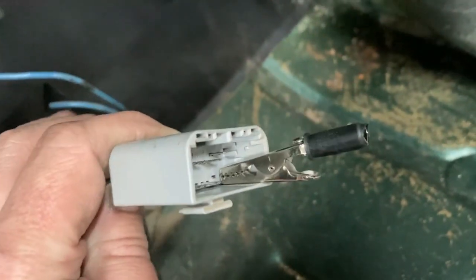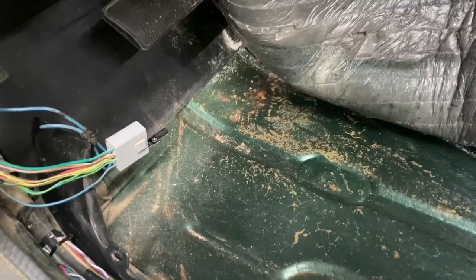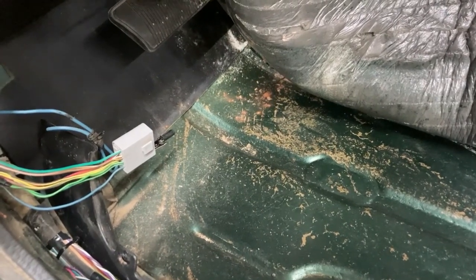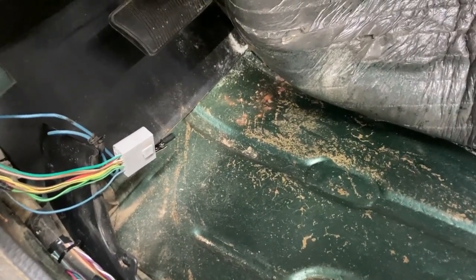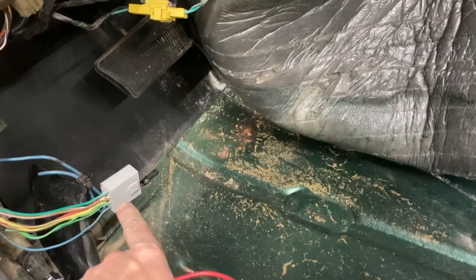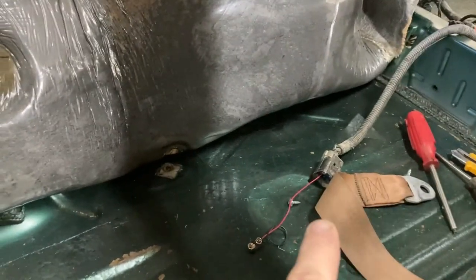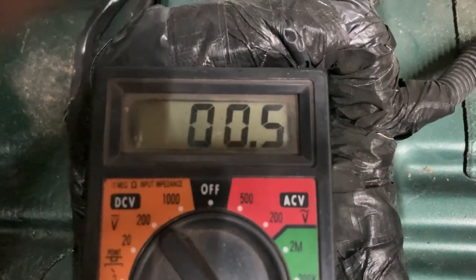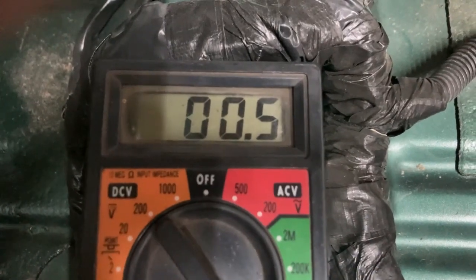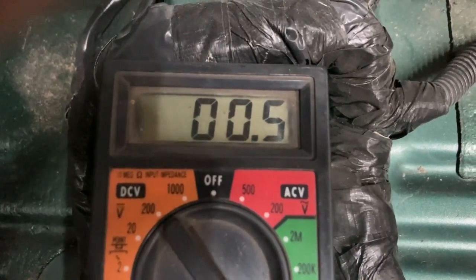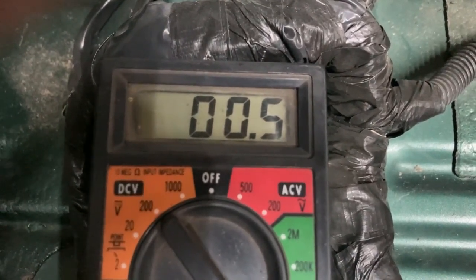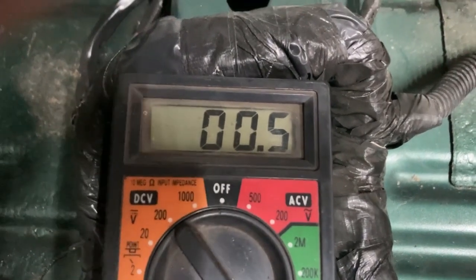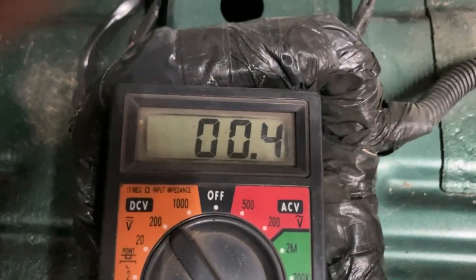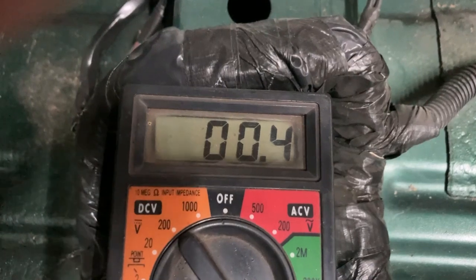I just got that alligator clip on the pin there, and I'm checking for continuity or resistance to make sure we have power from this end to that end. It looks like we're at around 0.5, which is good. The lowest reading I've received so far is about 0.3 - usually 0.3, 0.4 is where we're at. So I'm satisfied with that. That tells us this part of the wiring is good.